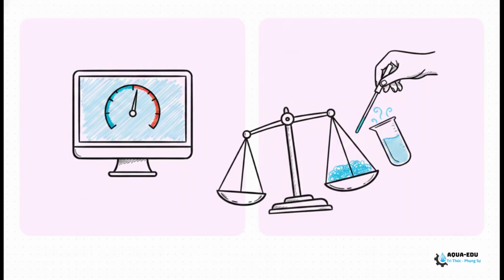Zeroing in on step 1 for a second, when you're comparing your SCADA online reading to a portable handheld meter or even indicator paper, what you're really looking for is the offset. If you notice a gap bigger than 0.3 to 0.5 units over a sustained period between what's on your screen and what's in your hand, boom, you immediately flag that online sensor as your primary suspect.